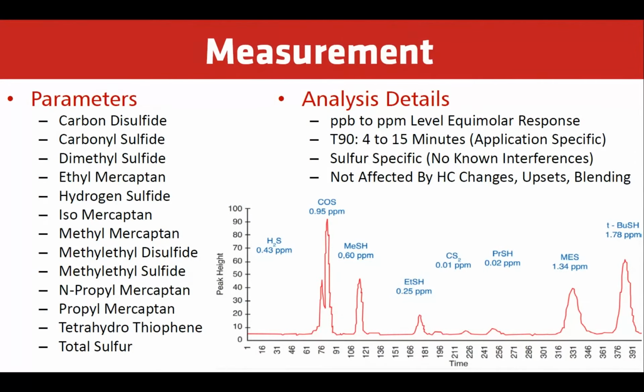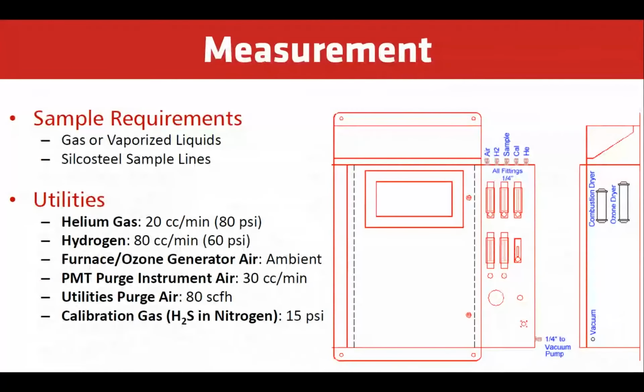T90: 4 to 15 minutes. Applications: sulfur specific, no known interference, not affected by hydrocarbon changes, upset or blending. Sample requirement: gas or vaporized liquid, Silcosteel sample lines. The utilities require helium gas, basically 20 cc's a minute. Helium we'd like to have set to 80 psi.